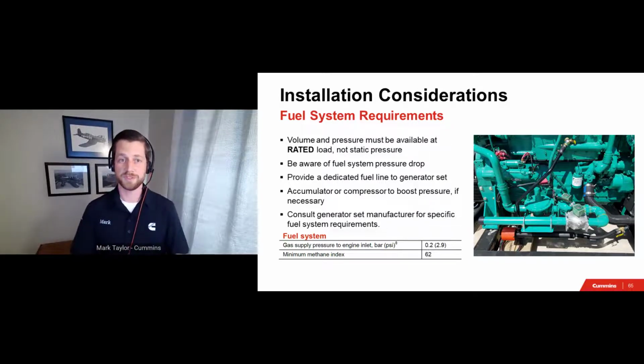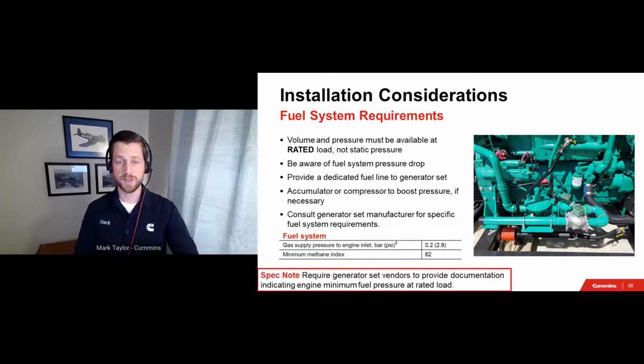Again, it is important that the supply can provide enough volume and pressure of fuel at the rated load of the generator set. That last part is an important distinction, as a seemingly okay pressure reading when the fuel is not flowing does not mean that it'll be appropriate at full fuel consumption. To mitigate these challenges, at times installations may need accommodations such as accumulators or compressors to boost the supply pressure. Of course, the minimum requirements for pressure and flow should be readily available from the manufacturer in their data sheets, and that should be an expectation on your side, and that should be available.